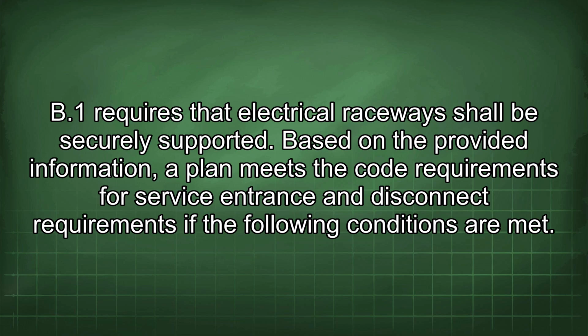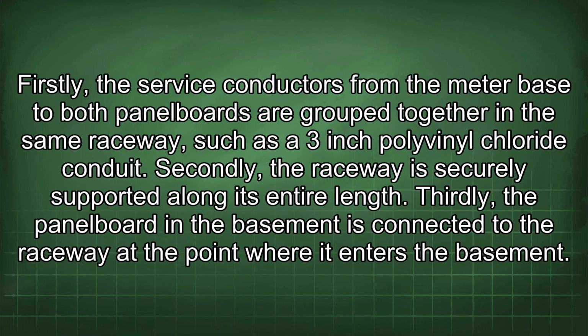Based on the provided information, a plan meets the code requirements for service entrance and disconnect requirements if the following conditions are met. Firstly, the service conductors from the meter base to both panel boards are grouped together in the same raceway, such as a 3-inch polyvinyl chloride conduit. Secondly, the raceway is securely supported along its entire length. Thirdly, the panel board in the basement is connected to the raceway at the point where it enters the basement.